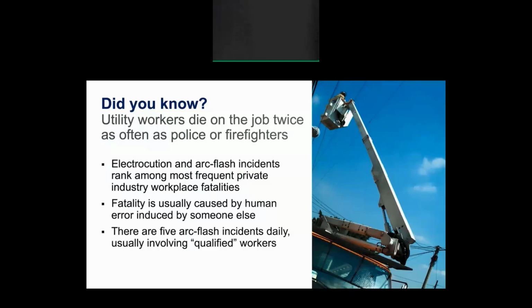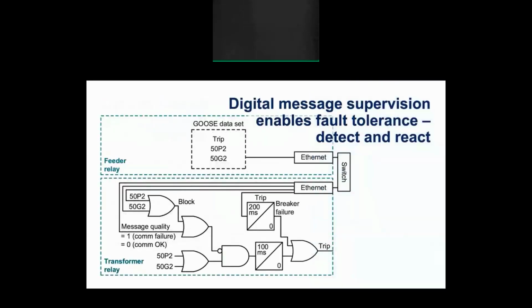Dangers to humans are a real challenge. For example, utility workers die in the line of duty twice as often as police officers or firefighters. Electrocution and arc flash are the most frequent private workplace fatalities. And the victims are usually qualified to be where they are working, but they're victims of someone else's design flaws. Digital messaging has a great advantage because we can detect the failure of the reception of a message. And this differentiates between a broken conductor being off or zero versus the lack of reception of the message. And in this example, on the slide, we have the ability in the receiving relay, the transformer relay, to supervise the quality of the information from the feeder relay. Now, when the message fails to arrive, we detect immediately the messaging is broken, and we adapt our logic accordingly.